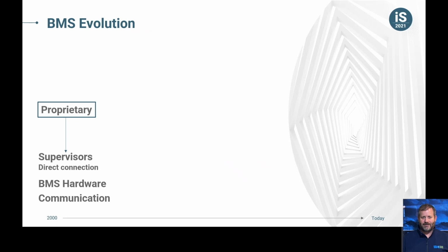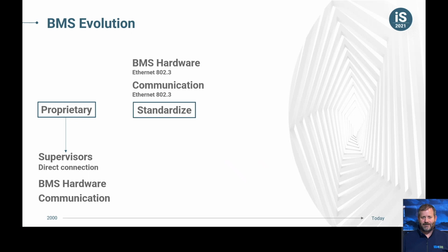If we look back at my last 15 years, when I started, all the systems were proprietary: supervisors were direct connected, BMS hardware was proprietary, and the actual communications connecting controllers were proprietary as well. The next stage was standardization of the communications. Since 802.3 led the way in speed, BMS products and infrastructure products started to adopt it. So we saw versions of BMS hardware with Ethernet. With that, supervisors then got detached from the BMS hardware and put onto the communications network, giving them more flexibility.